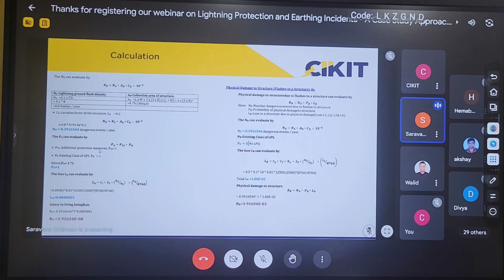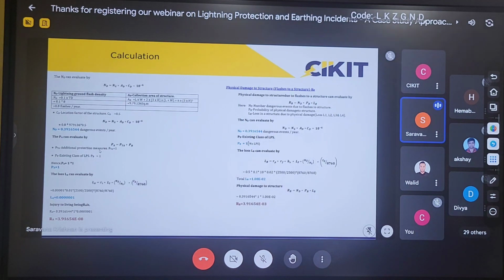So by performing this calculation, we have to repeat it. Here I have performed the calculation with PB equal to 1. Second, if I am going for level 4, I have to perform the calculation with 0.2. Again, if the value is higher, I have to repeat the calculation with level 3. Then if the value is still higher, I have to perform the same calculation with PB equal to 0.02, which is for level 1. Our ultimate aim is to bring the value lower than the tolerable limit. So this is how we have to perform this risk assessment calculation.